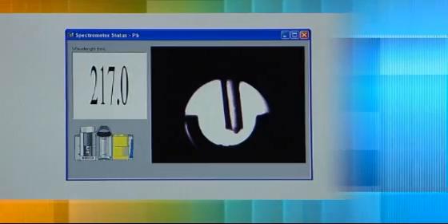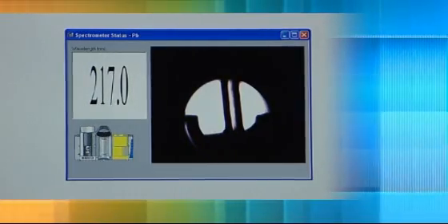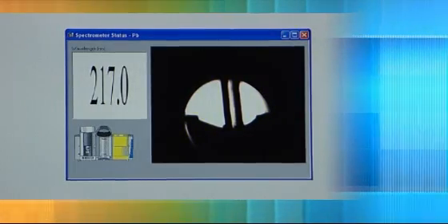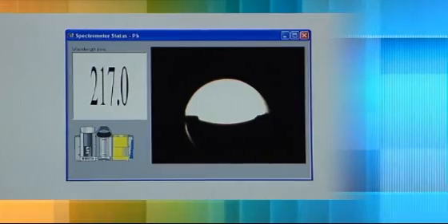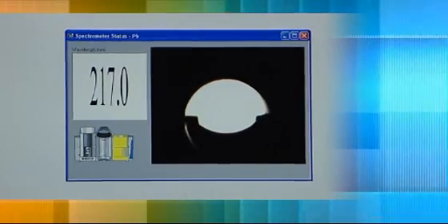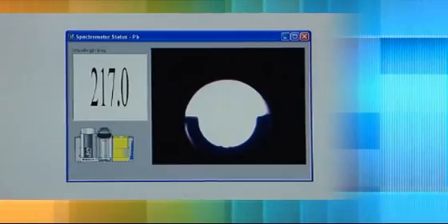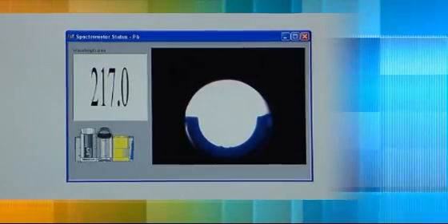With GFTV, it only takes a few moments to optimize the injection depth of your sample. You can watch an injection to ensure that your sample is smoothly deposited in the cuvette, and the wizard will automatically optimize the ash and atomize temperatures.